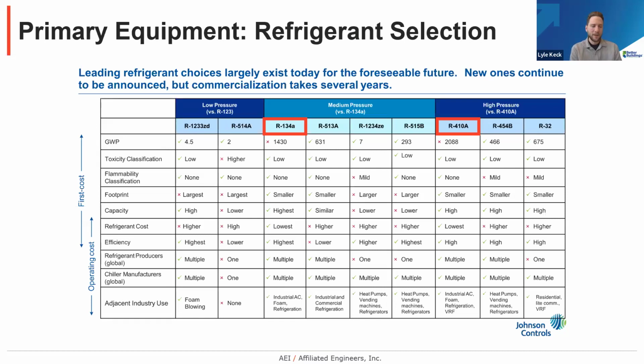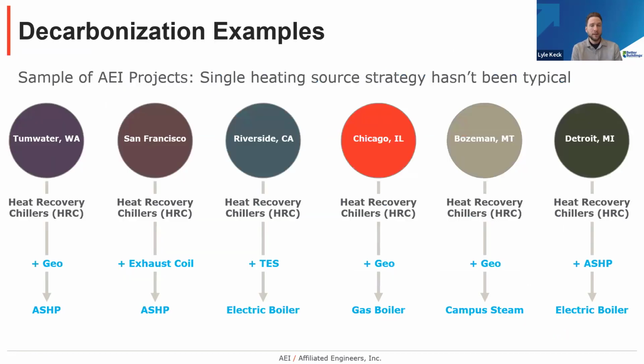So on the left-hand side here, you can see that there are a lot of different considerations and trade-offs for selecting these. You have capacity considerations, there are space requirements, you might have different flammability classifications which impact the cost or the types of systems surrounding the space that the equipment is in. And so if we were to go, let's say, to an ultra-low R1234ZE, which has a GWP of 7, it does come with a larger footprint and a lower capacity relative to 134A or what's on there today. So even if your facility was planned for expansion, you may have different needs just given the new equipment that's available today. Next slide, please.